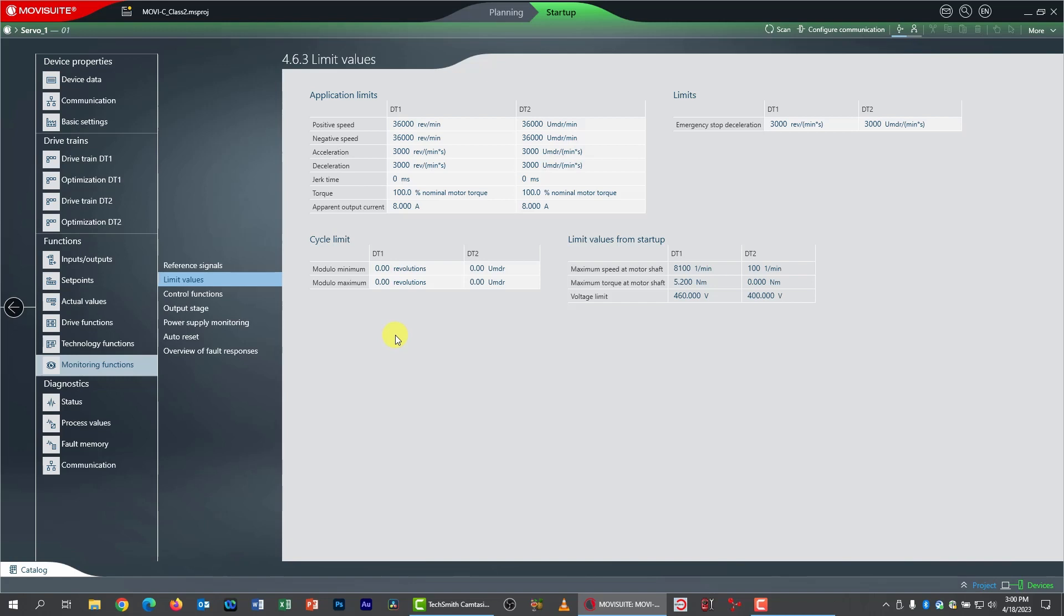And also we need to set our application limit ramp values. Now, 36,000 RPM is very fast and definitely well beyond what our servo motor can do. So I'm going to change this to its nominal speed, which is 4,500 RPM. And I need to change it for both directions.